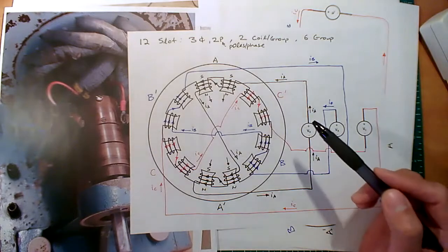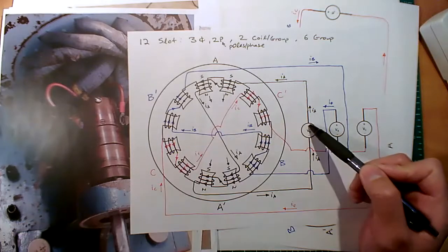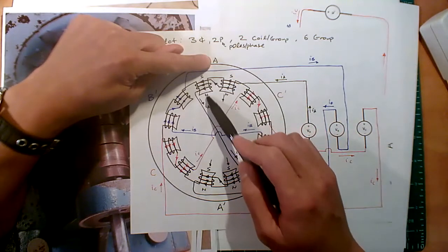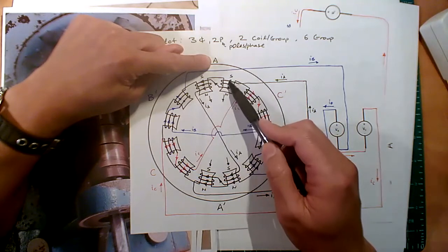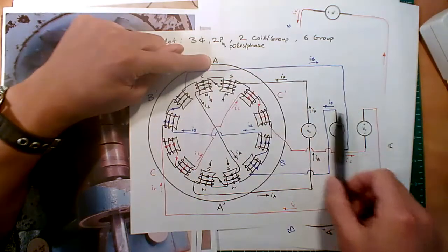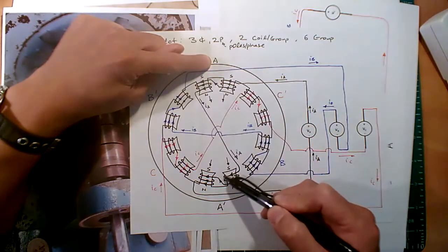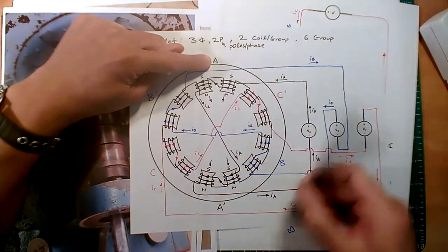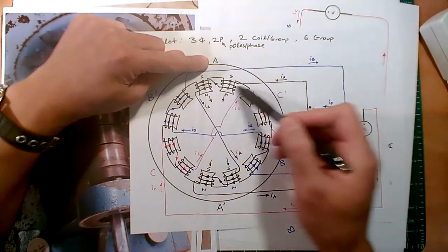So let's follow and trace out how we would connect this. Coming out of the A phase, the positive terminal, let's go to the A branch, right? And notice when I have positive current coming out of the A branch, I'm going to create a magnetic field that's going down. If I want two poles, this has to be my A prime, and look how it flows out of here into there. And in order to make that happen via Ampere's law, I need to connect the end of this like so, right? And you can see that everything is in the same direction here, and then it can come back home. Does it matter if I connected this coil first and then this coil? No, it's all in series.